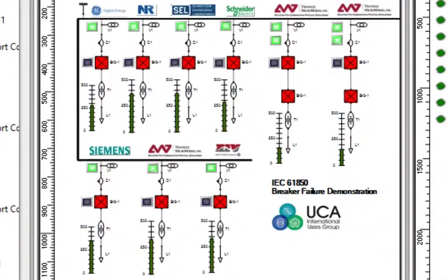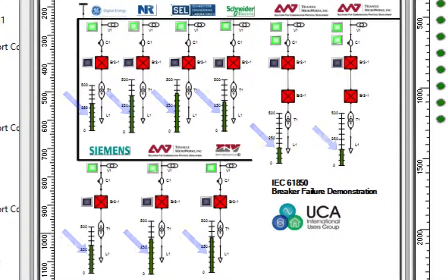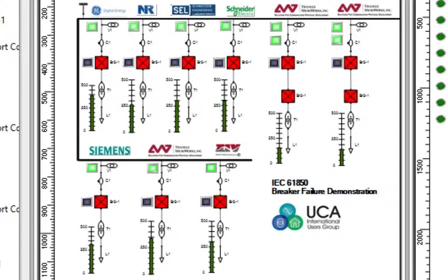In the single line diagram, green indicates the breaker is open and red indicates the breaker is closed. A script on each server will set the current to a base value plus a random load component if the breaker is closed. These values are being sent by the simulated devices and are being read by IEC-61850 clients in DTM, which uses Insight to update the display.